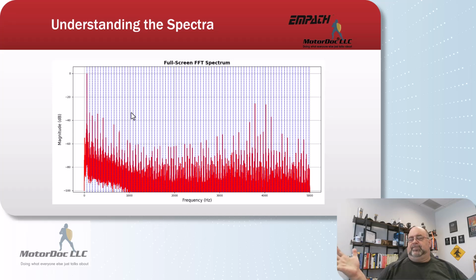When I start looking at a larger spectra, now I limit it. This is off of the Empower system, which is a 44.1 kilohertz sampling rate. My Nyquist is half of that, so technically it's 22 kilohertz. But we chop it down to 5 kilohertz for purposes of maintaining your eyesight, which covers most things, including identifying the firing frequency of a VFD, which is right here. That's about 3,800 hertz, and then allows us to zoom in on other conditions.